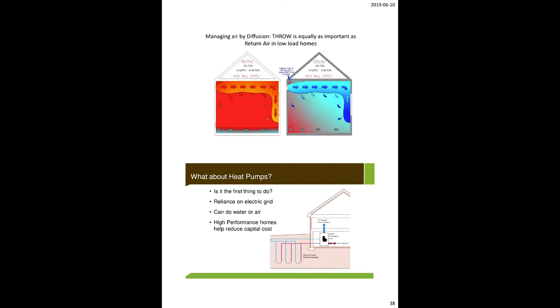This is the air source heat pump at our house. Our net zero home, way oversized, it's overkill, but we're doing a study with Mitsubishi. This is actually a commercial-based system. A couple of things on the residential side. Manufacturers will only give you the HSPF performance levels for zone 3 and 4. They will not give you your correct zone. So they're going to tell you heating seasonal performance factors that are incredibly high. You've got to derate them. And good luck finding the data. I know Mitsubishi and Fujitsu, you might be able to find it, but you need to look for the right data.